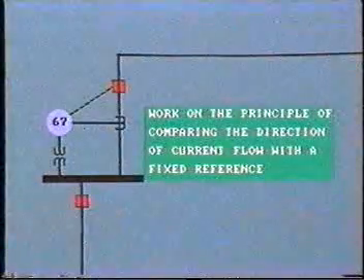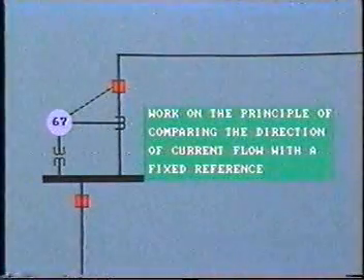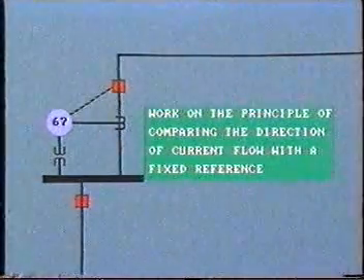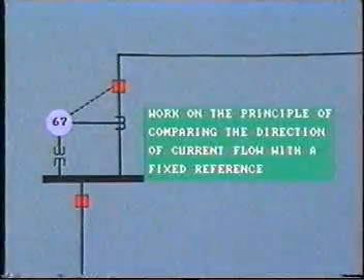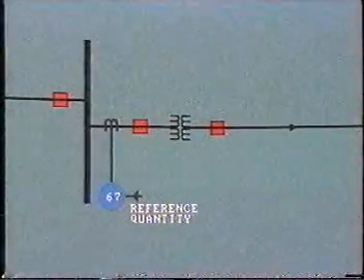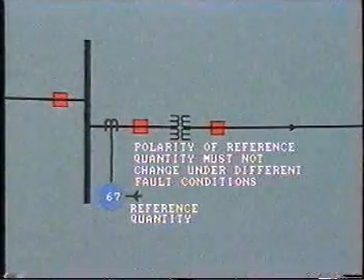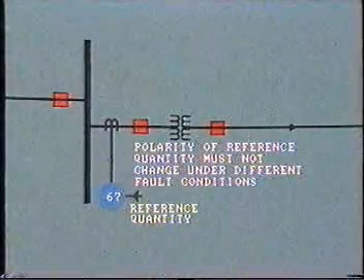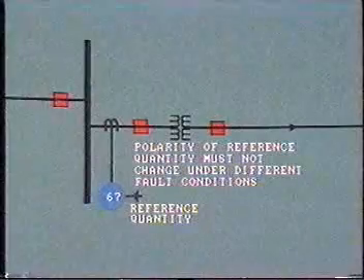There are several different types of directional relay, but they all work on the principle of comparing the direction of current flow with some fixed reference, which may be voltage or current. To be more precise, it is usual to compare the phase angle of the current in relation to that of the reference. The important point is that the polarity of the reference quantity, be it voltage or current, must not change even under different fault conditions.